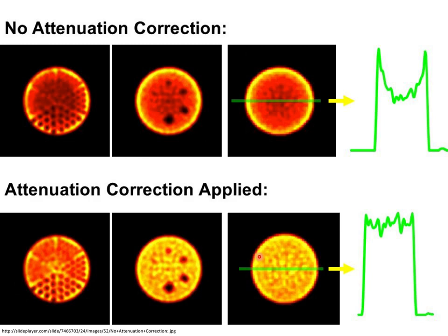Right? So it's a big problem, which is why much of SPECT, and certainly PET now, is done in combination with a CT scan. So instead of a SPECT scanner, you get a SPECT CT scanner. You do a CT image, and then you put them in the SPECT scanner, and you use the CT image to correct for the absorption of the radiation in the SPECT scanner.